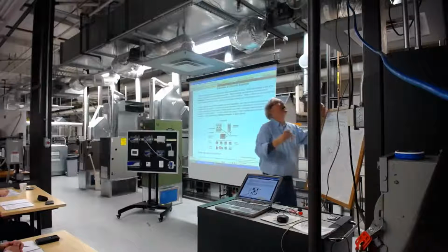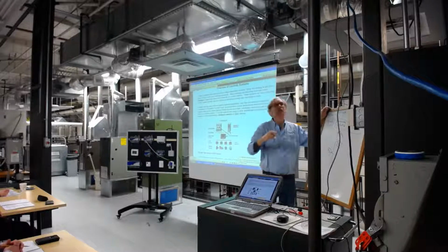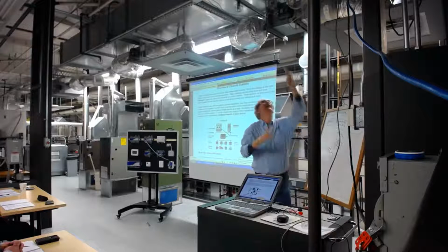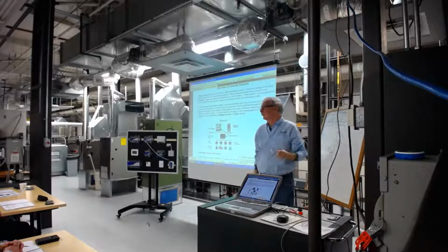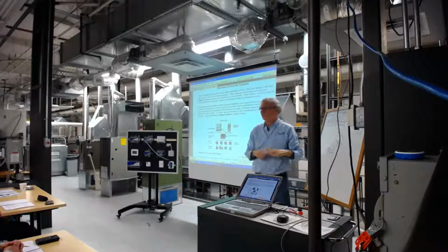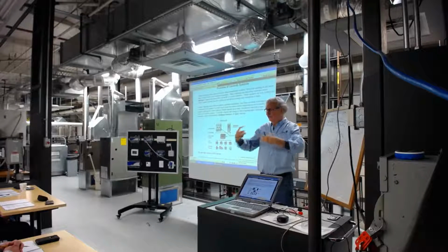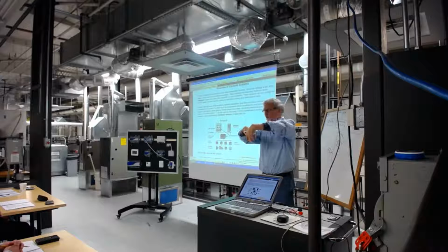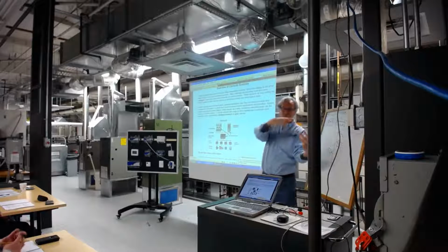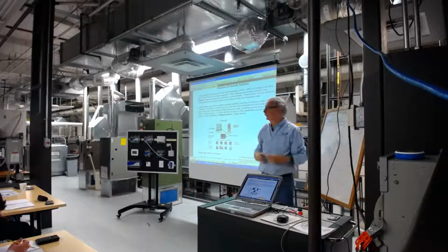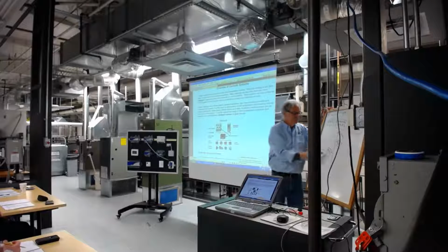Okay. So that little guy right there is a field controller. There's a field bus. Right now it's disconnected, but that would be the field bus. It's daisy chained. You cannot do a star configuration. It's daisy chained in. So 3 wires into one connector, one controller, 3 wires out to the next controller, and so on and so on.